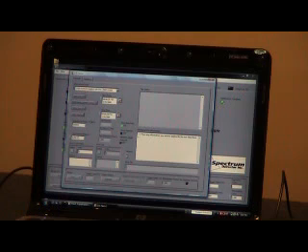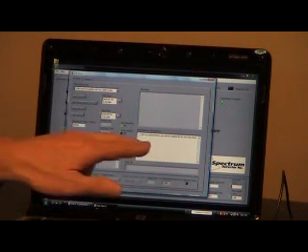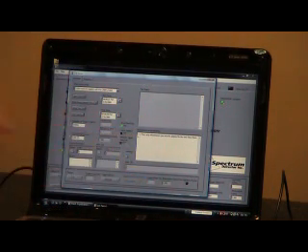And what the software will do is it will activate itself and establish communications with the box, and it will wait until the first test is to be run. It will take tests at those intervals and store them in a file that you name. Any information that you want to put in that file on top of the information the box is storing, which is all of your pulse data as well as the setup and the state of the box when the data was taken, will be appended to it if anything you can type into this window, just something maybe to jog your memory as to what the test was for.